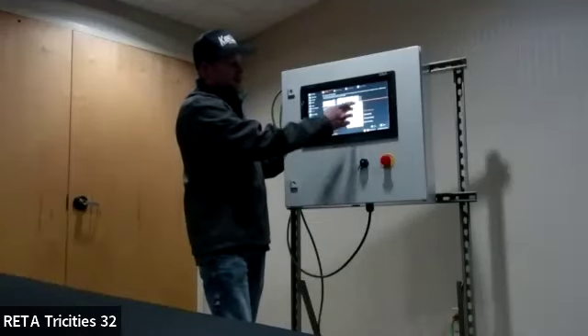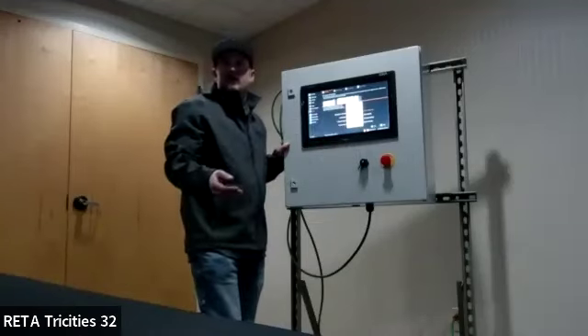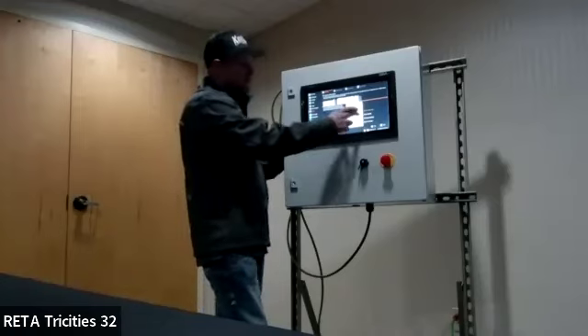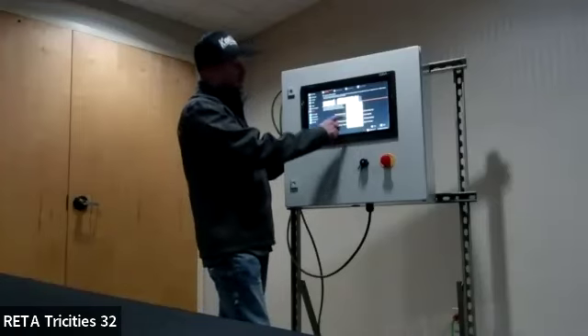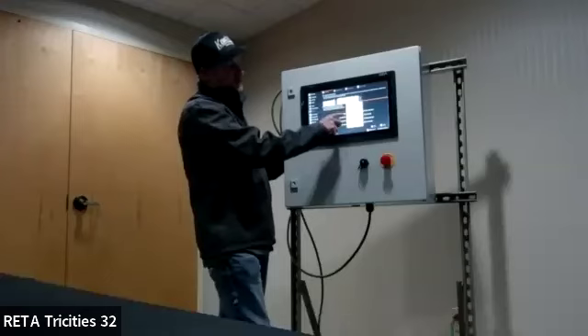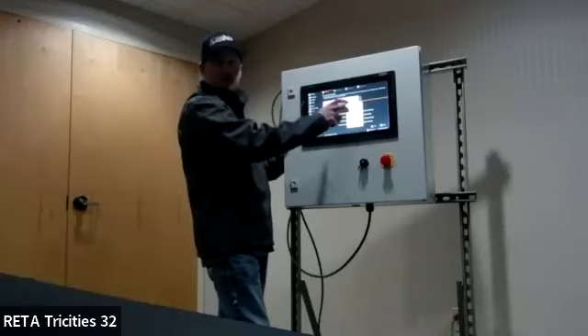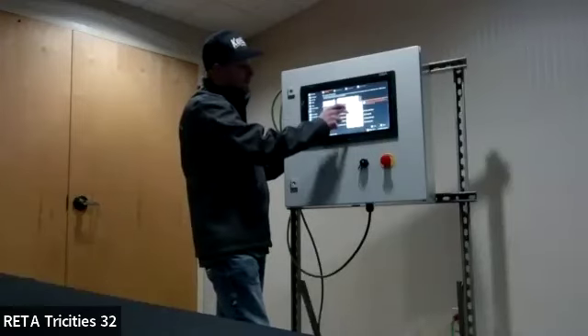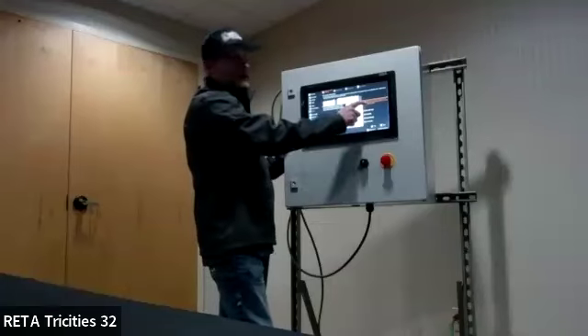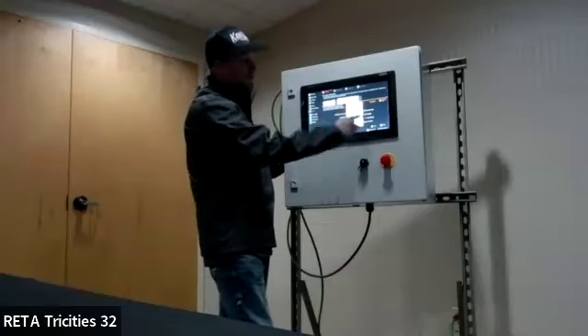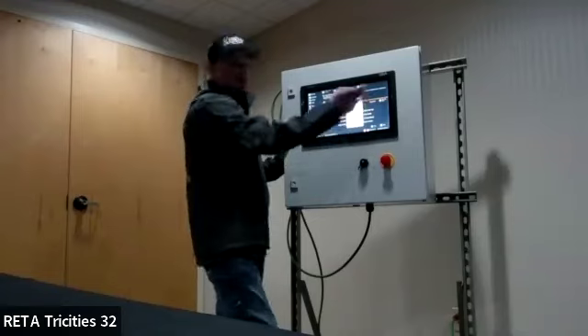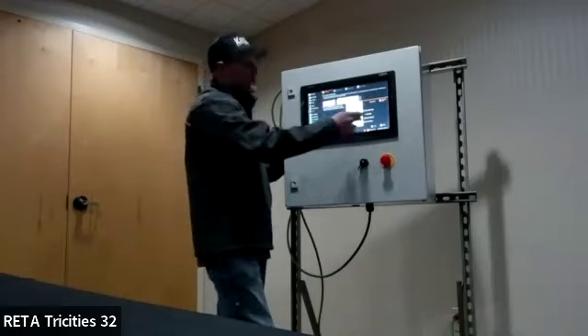Copy. This is also where you would bump check the motor for the compressor. So if you change out the motor, you want to bump check it with it uncoupled. You click, this says compressor motor start right here, and there's some arrows making a circle here, you click it. And then you have to come over here and click this one more time, and it's gonna run it for 30 seconds, and you can stop it or let it run full 30 seconds.